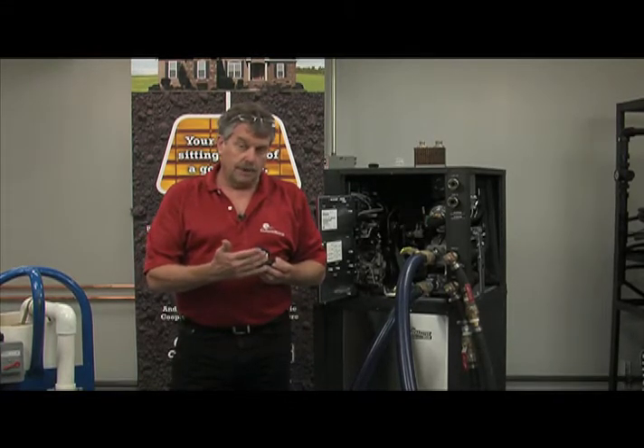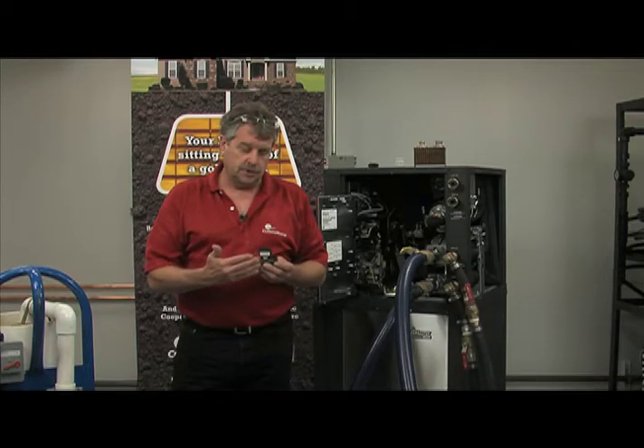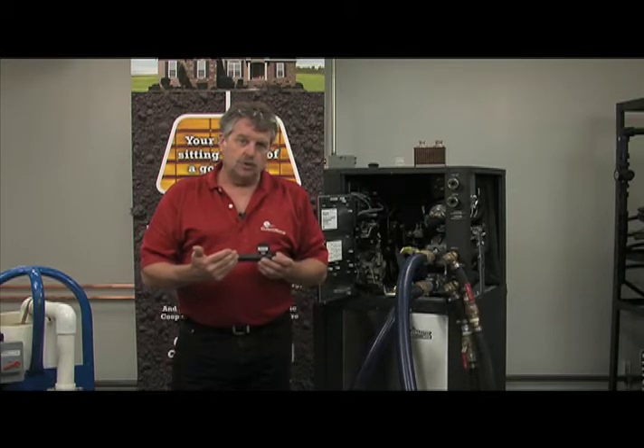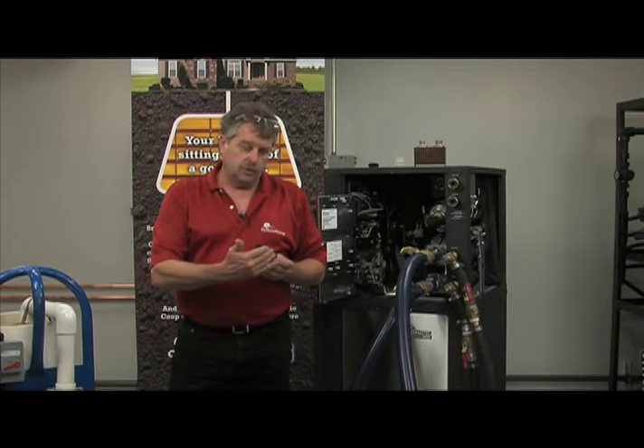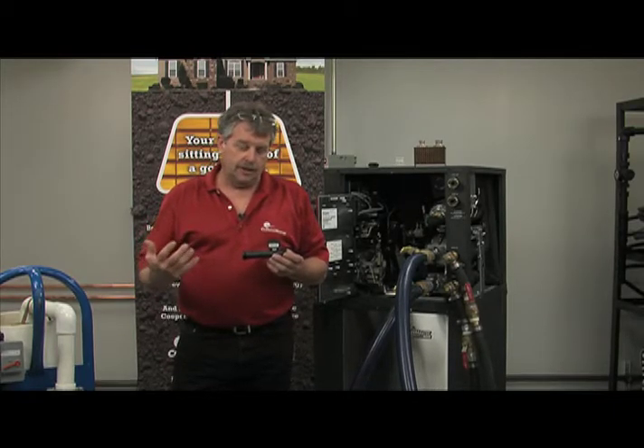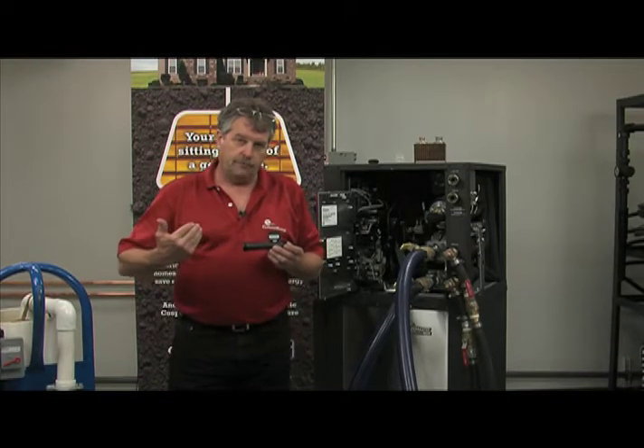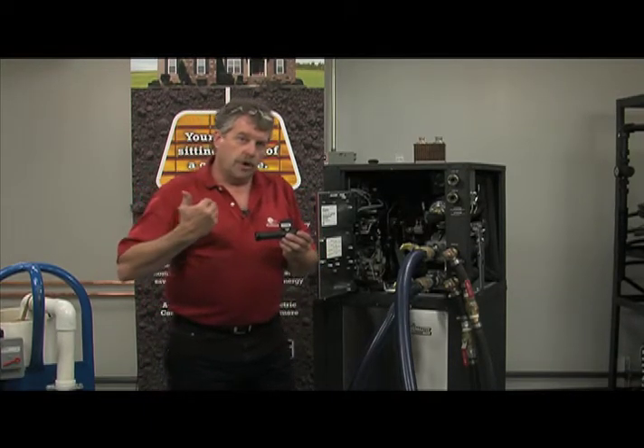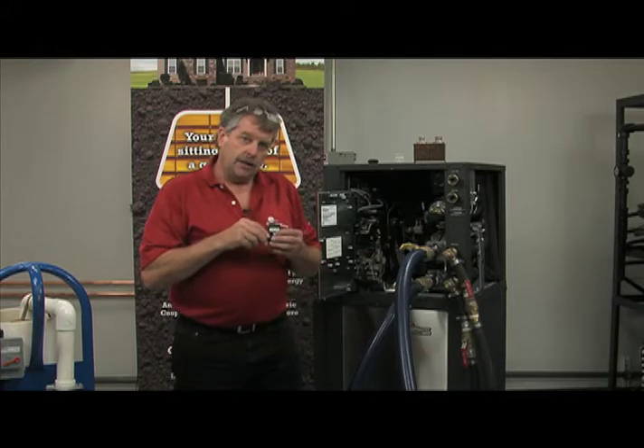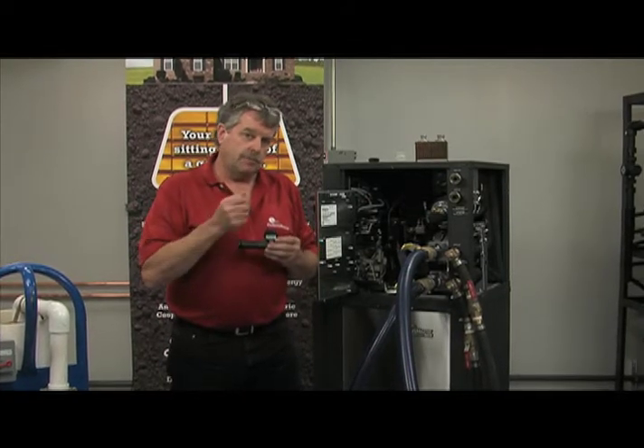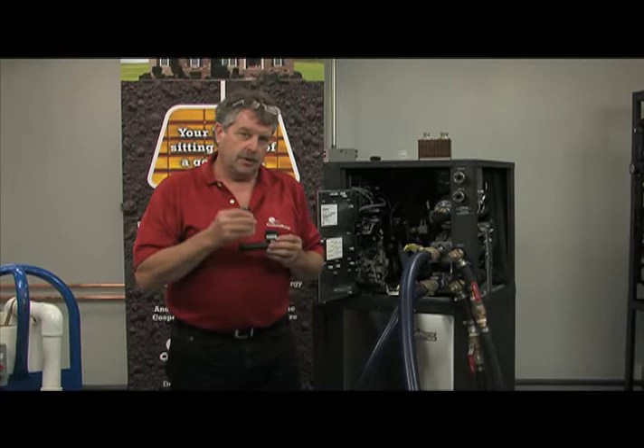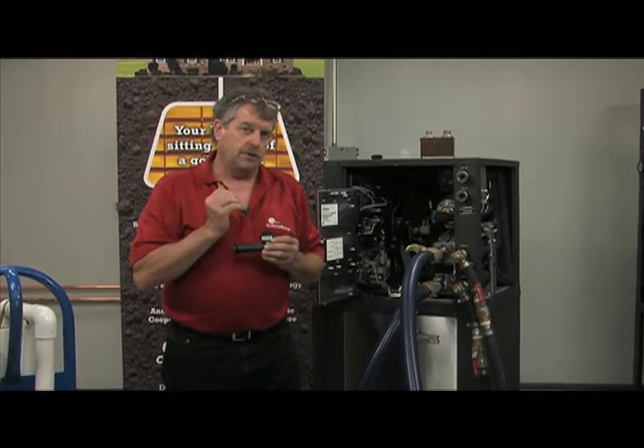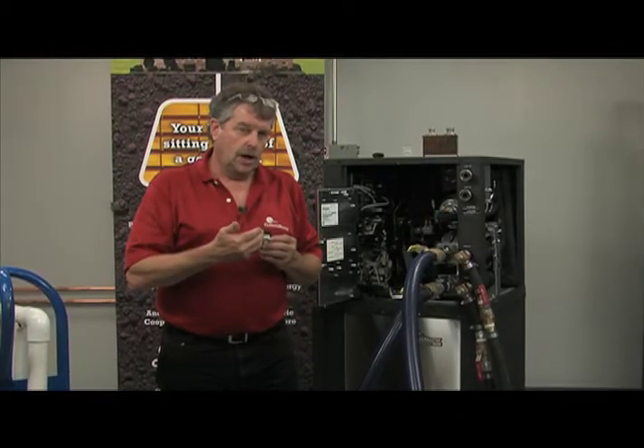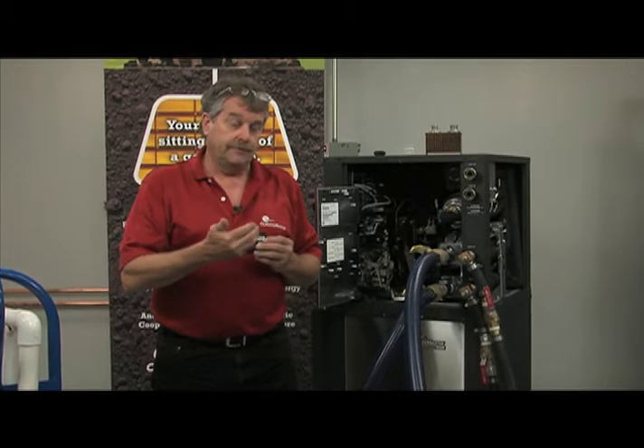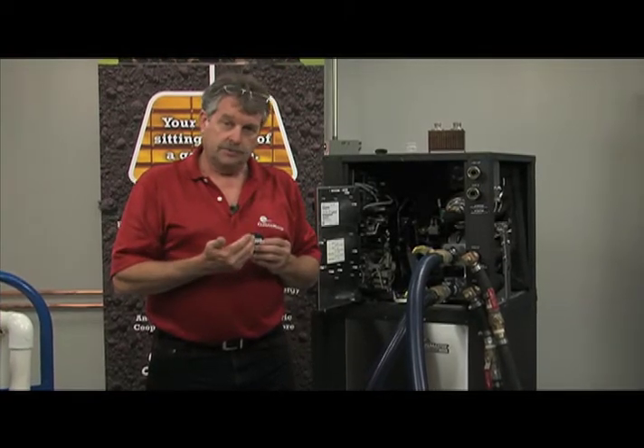That will also compromise this, but the one that we have found most importantly that causes the issues with this sensor is not slowly removing that pocket of air. So if you slam that flow from a flush cart full force in there, that wall of water coming in with that air behind it, when it hits that sensor, it actually pops that membrane in there. It's a little bit like someone popping your eardrums, okay? It actually causes the sensor to be then defective, and you'll have to go through a replacement procedure.